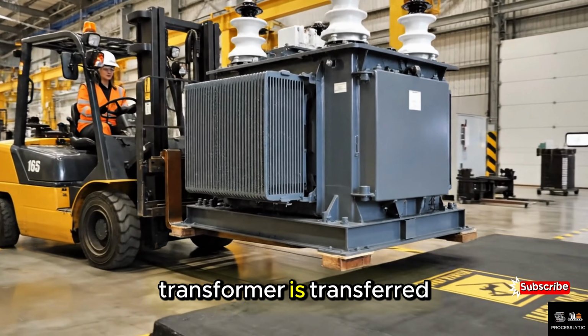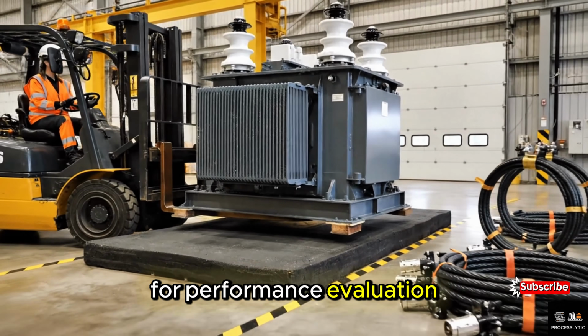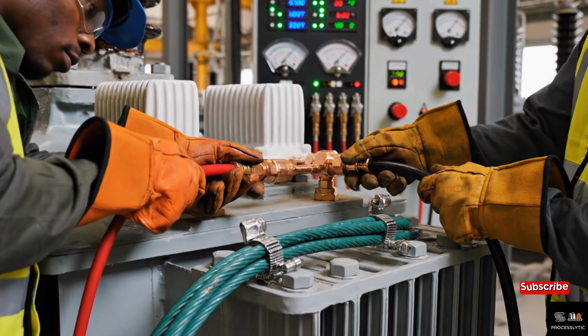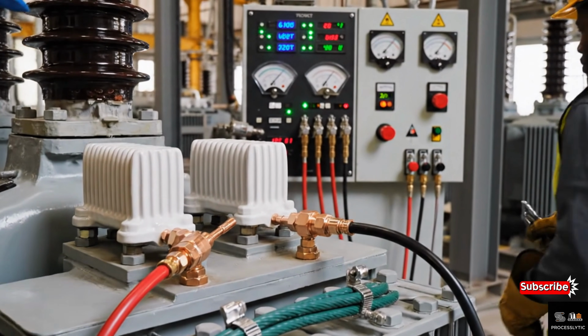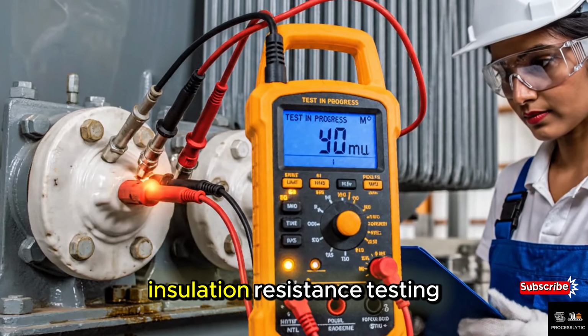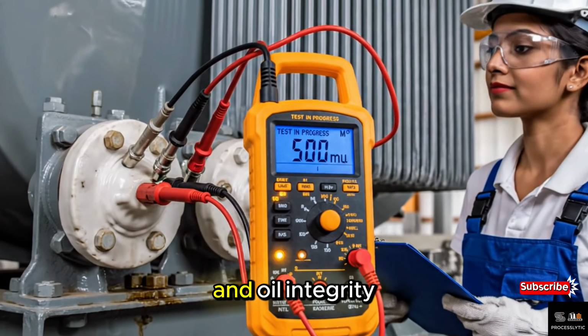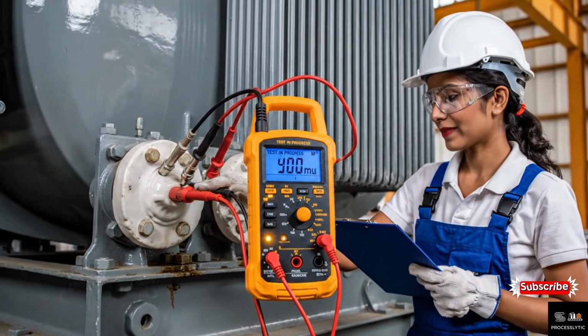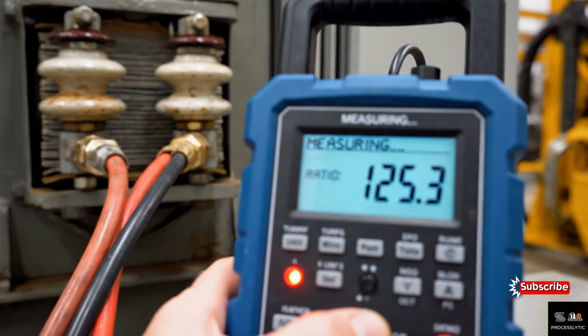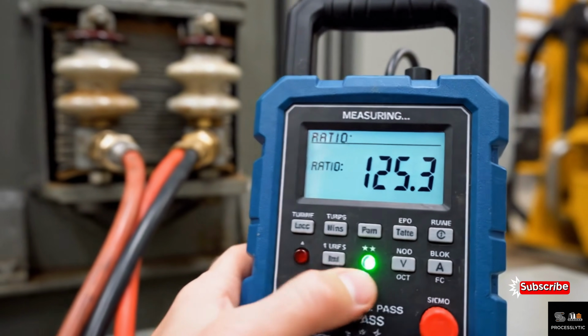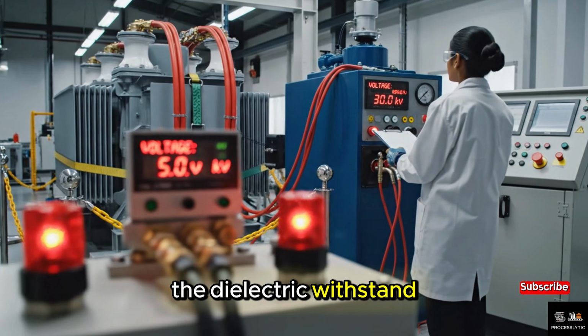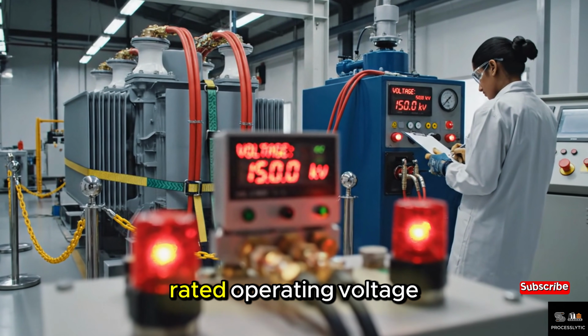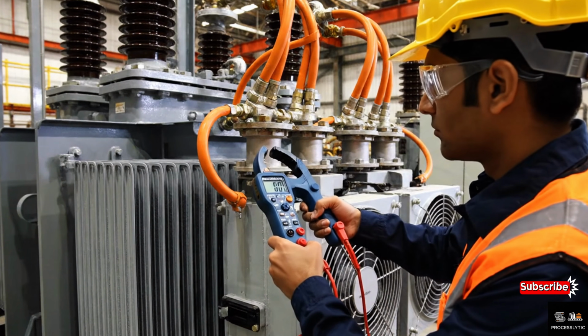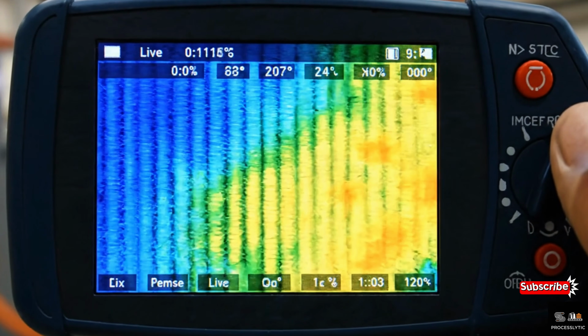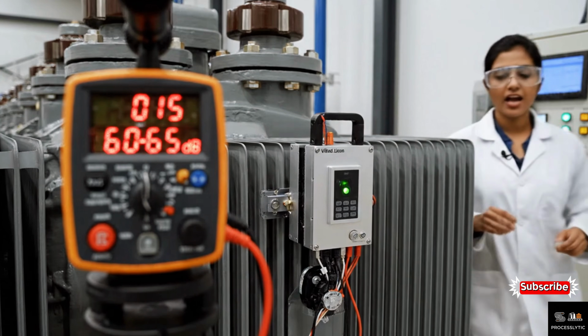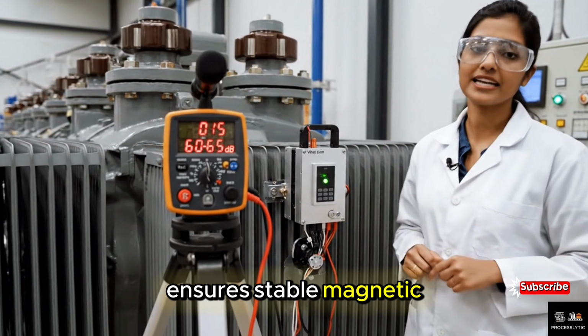The oil-filled transformer is transferred to the electrical testing area for performance evaluation. Insulation resistance testing confirms that winding insulation and oil integrity meet safety standards. The dielectric withstand test verifies the transformer's ability to handle rated operating voltage. Acoustic and vibration testing ensures stable magnetic core performance under load.